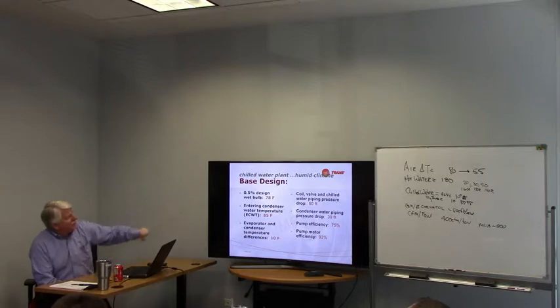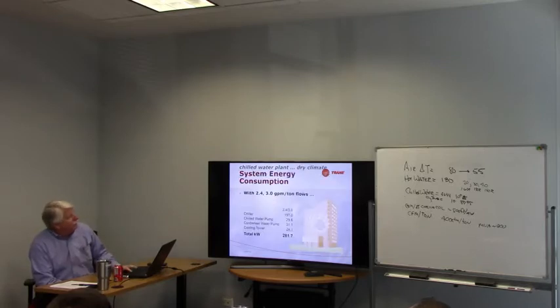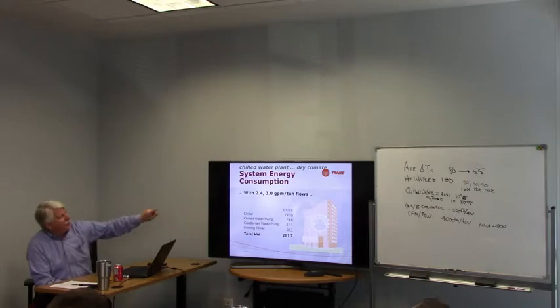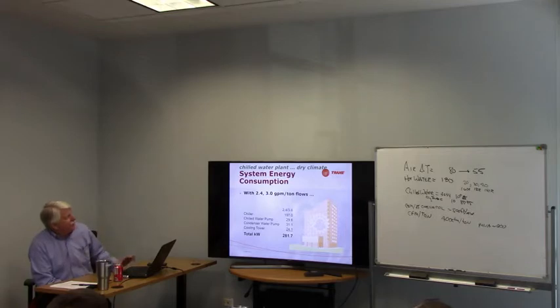Now this is just some basic design information that we're using for the basis of the study here. With 85 degree entering condenser water, 10 degree temperature differences on evaporator and condenser. What we're going to do is look at the effect of different flows on kW. And here at a 2.4 and a 3, which is our baseline old design, it's 281 kW. If we go to 1.5 on the evaporator and 3 on the condenser, it drops our kW down to 276. You can see here if we go to 2.4 and 2, it's 278, so you don't get quite as much savings there.